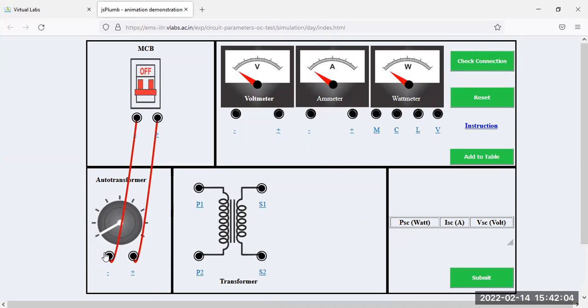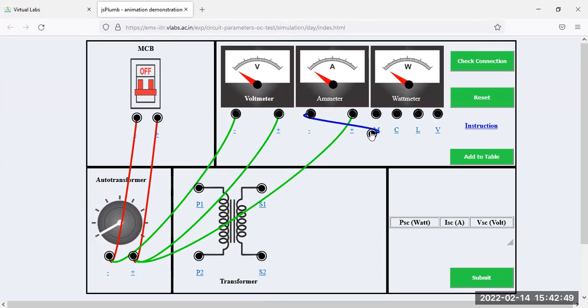And similarly, for the measurement of this voltage, you need to connect one voltmeter in parallel. So the positive polarity of this voltmeter is connected to the positive polarity of this auto transformer, and the negative polarity of this voltmeter is connected to the negative polarity of the auto transformer. Now for the measurement of current during the short circuit test, we require one ammeter connection. So take the positive polarity of this ammeter to the positive polarity of the auto transformer, and from the negative polarity of the ammeter, connect to the wattmeter M terminal.